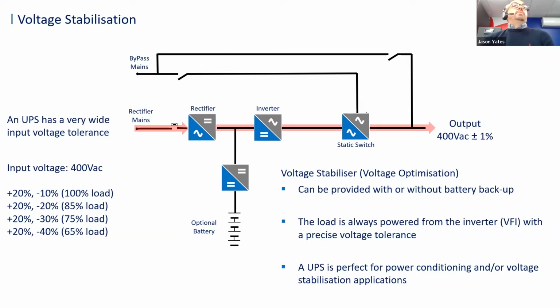The term online means that the load is being permanently powered from the inverter. One of the benefits of an online dual conversion UPS system is a very wide input tolerance in terms of voltage and frequency. As you can see there, typically a UPS system will have an input tolerance of around plus 20% down to minus 10%. But at lower loads, or if the UPS is oversized, that tolerance can be increased to plus 20% down to minus 40%. One of the key benefits is that no matter what happens to the incoming supply, the UPS will always deliver a predefined, in this case, 400 volts AC with a tolerance of plus or minus 1%.